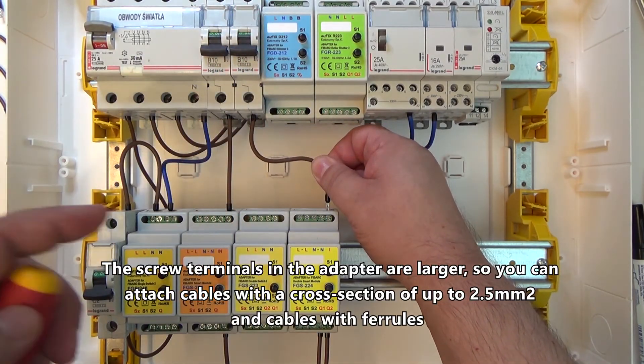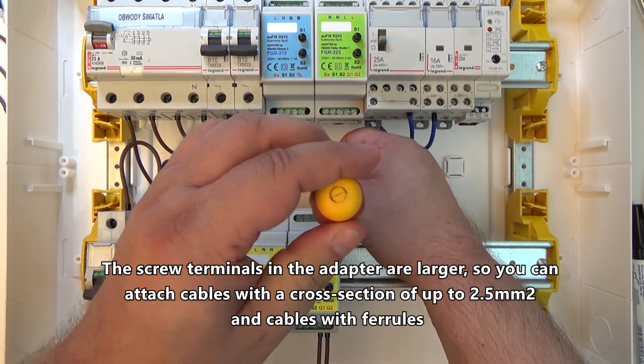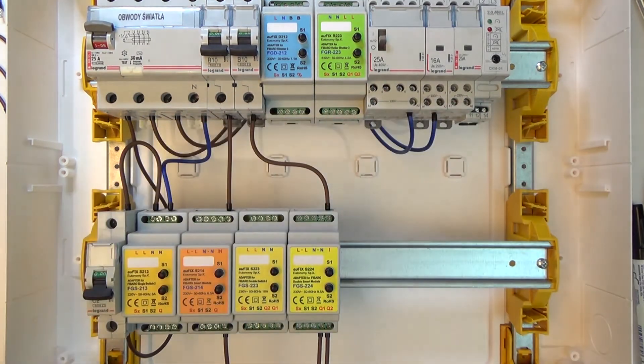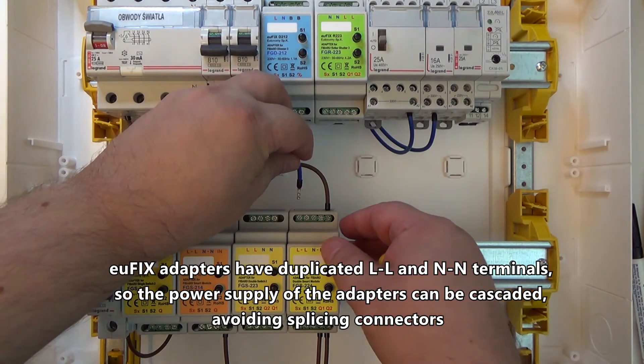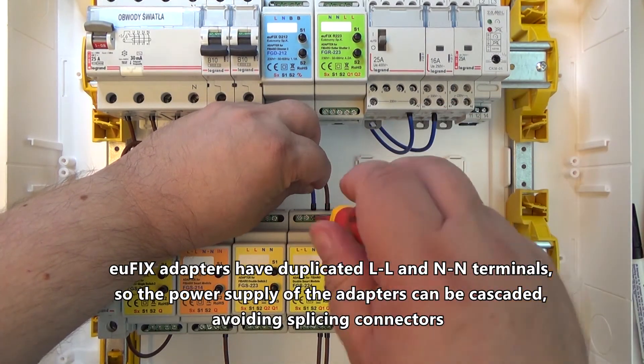The screw terminals in the adapters are larger, so you can attach cables with a cross section of up to 2.5mm² and cables with ferrules. The euFIX adapters have duplicated line-to-line and neutral-to-neutral terminals, so the power supply of the adapters can be cascaded, avoiding splicing connectors.